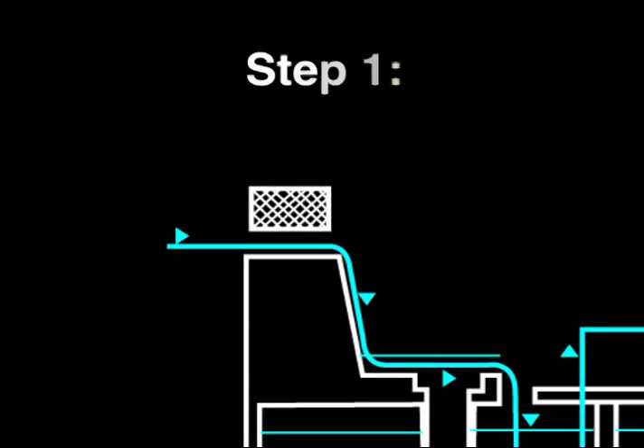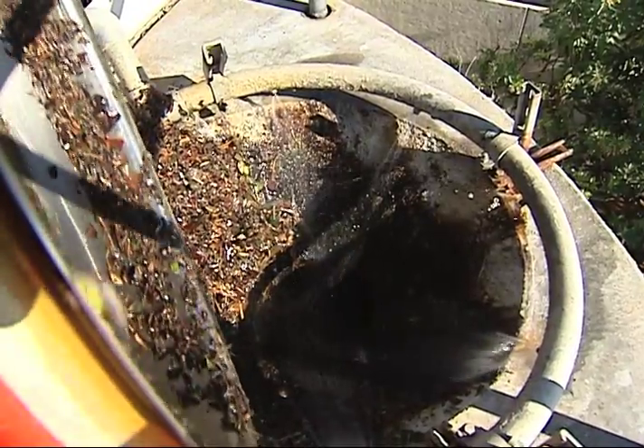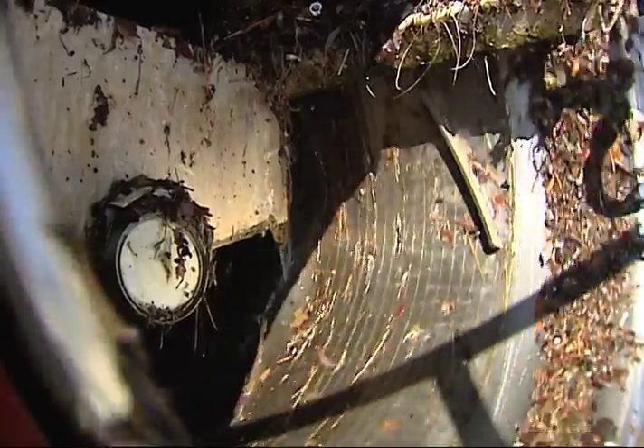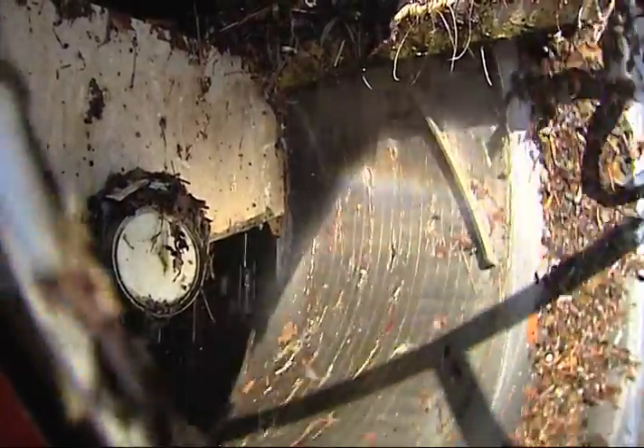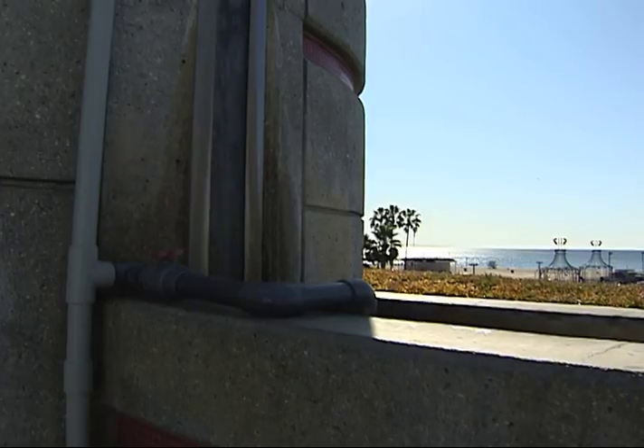Step one of the treatment process is sending the incoming water through the rotating drum screen, which removes trash and debris. Inside this device is a five millimeter screen. The solids are trapped inside the screen drum while the filtered water passes through and out of this device. The solids are moved to one end of the drum and delivered to the sanitary sewer. For each of the first four treatment steps, there is an effluent that goes to the sanitary sewer. Water leaving the screening treatment stage exits through the first of three waterfalls.